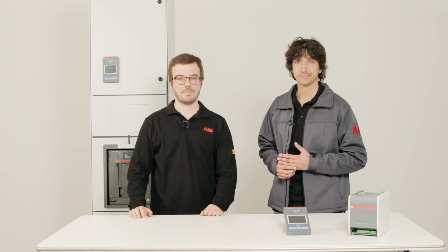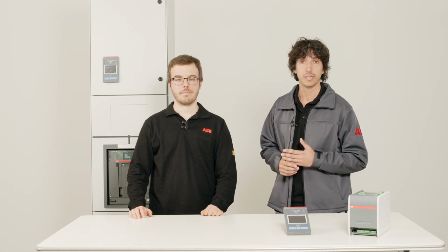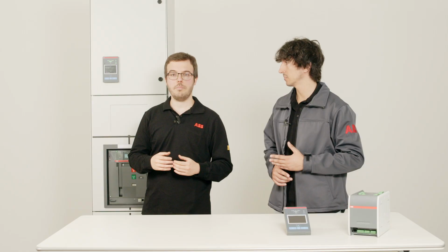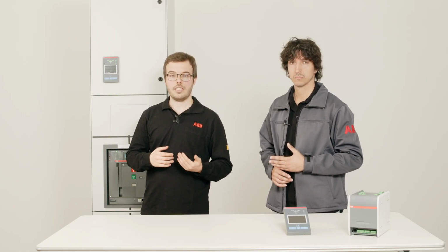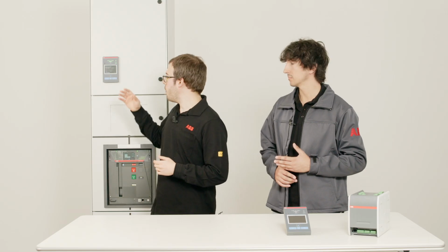Good morning, everyone. Today we're going to focus on how to configure TruCONTROL 2.0, introducing a new feature called auto configuration that will enable you to save time and cost. Thanks to the automatic configurator, the TruCONTROL 2.0 is able to automatically detect and set important parameters like the rated frequency, the rated voltage, the phase sequence, the neutral pole location, and the power distribution system for both source 1 and source 2. We will now see how to perform the automatic configurator on our device.